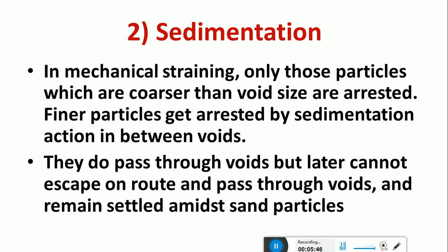Okay, then we have the process of sedimentation. Here only those particles which are coarser than the void size are arrested. The finer particles get arrested by sedimentation action between the voids. Along with the mechanical straining, the small spaces between the sand grains act as small sedimentation pockets. Because of that, the particles get arrested in the spaces present between the sand grains, and they can be removed out after the filtration process.